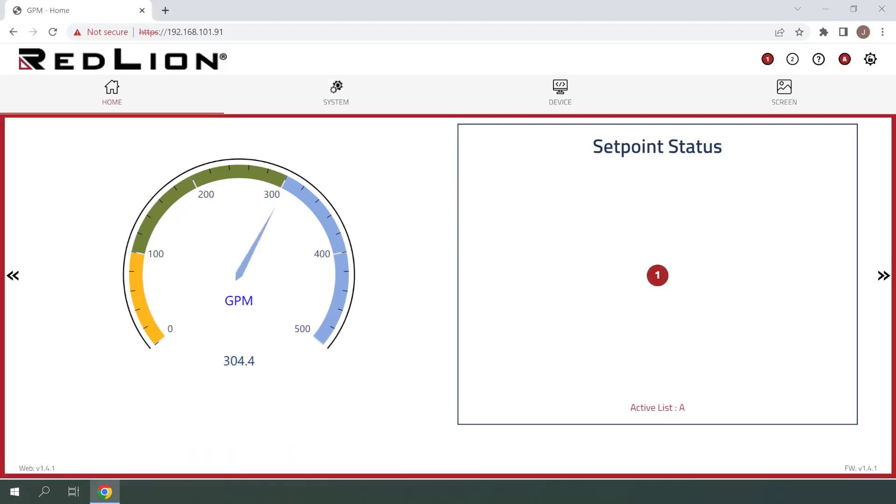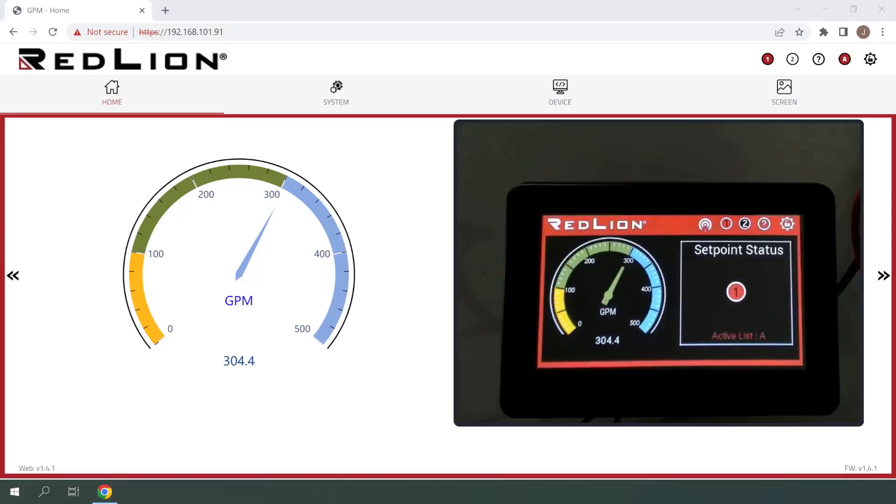As you can see, the setpoint alarm triggered as expected when we went above 300 GPM, so things are working so far. Here's a quick look at the PM50 unit itself, and you can see that the enunciator banner is visible there as well.